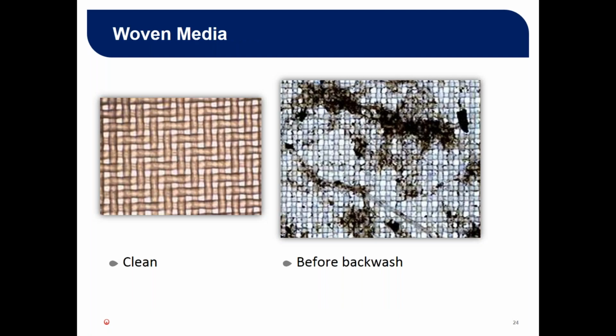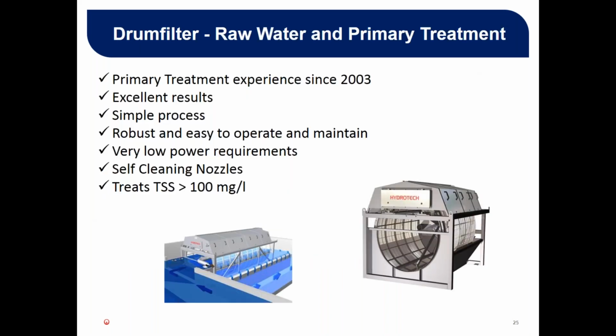So here's a microscopic image of the filter media. This is a 10 micron cloth. It's an absolute barrier, so solids just build up on it and they get sprayed off it. There's nothing fancy about it. If the solids are larger than 10 micron, they're not going to get through, or whatever micron size is in the filter panel.